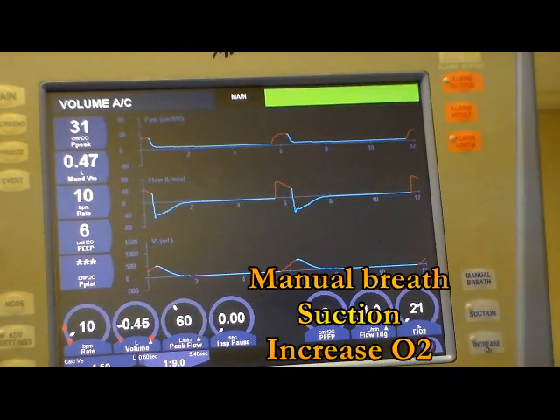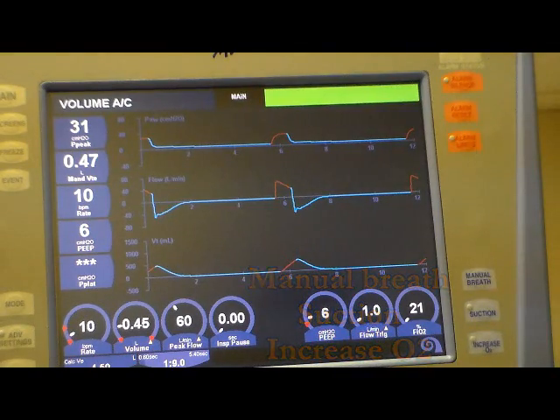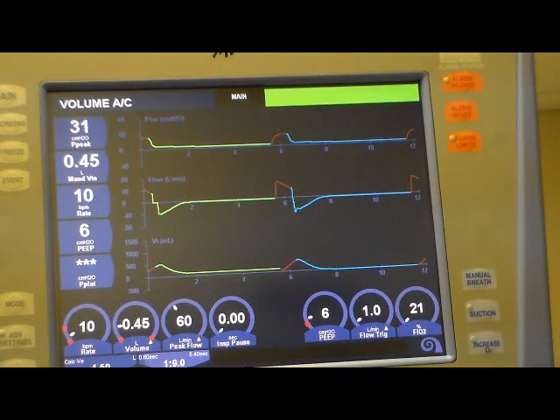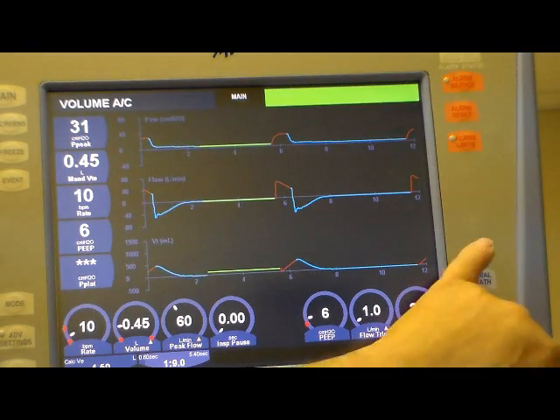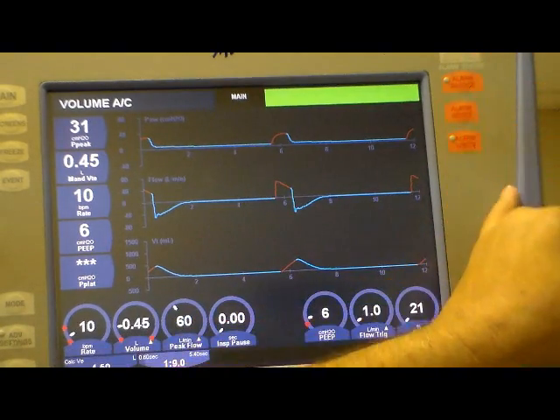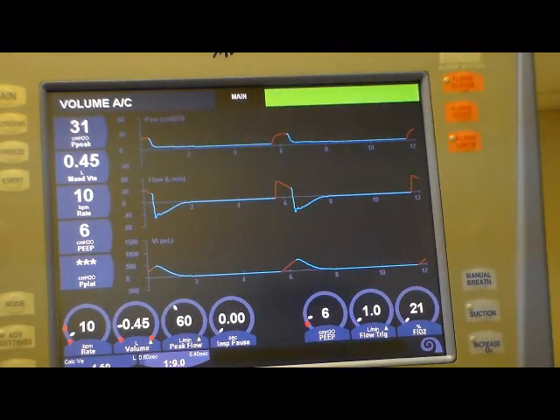Or you can go to increase FiO2 with some patients, like neonates. You don't want to go from 30% oxygen all the way up to 100%, but maybe you want to only go up to 40 or 50. Well, you can preset that amount so that you don't over oxygenate a patient and really mess up their status. Okay, so these are little action buttons: alarm silence, alarm reset, alarm limits.